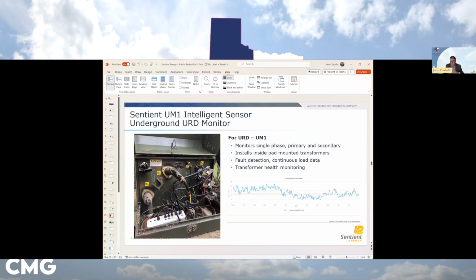The UM1 is great for continuous monitoring of the transformer. We're looking at both the primary and the secondary side. Because we're able to continuously monitor that transformer, that feeds right into the transformer health. As you overload a transformer, you start to break down the insulation and reduce the life of the transformer. This applies to many pole mount units too, but for the pad mounts, you see that many transformers are becoming more and more overloaded as more load gets placed on the grid.